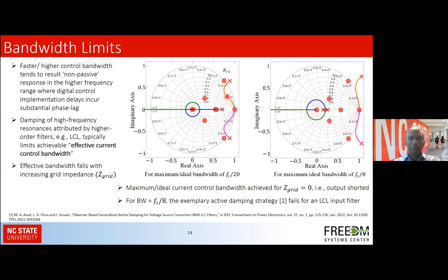Whereas if we increase the bandwidth to go up to fs over 8, the plot on the right shows that there is no stable operating point, as all of those are outside the unit circle. So faster and higher control bandwidth tends to result in a non-passive response in the high frequency range, where in the digital control implementation there would always be inherent delays and phase lag. And the damping of the high frequency resonances due to these higher order filters limits the achievable effective current control bandwidth. Also, the bandwidth falls with increasing grid impedance. So that's why we have a limit on the bandwidth that can be achieved for the current controller. And on top of that, of course, is the PWM frequency, and some inverters can also be frequency limited in the higher power and voltage ranges.